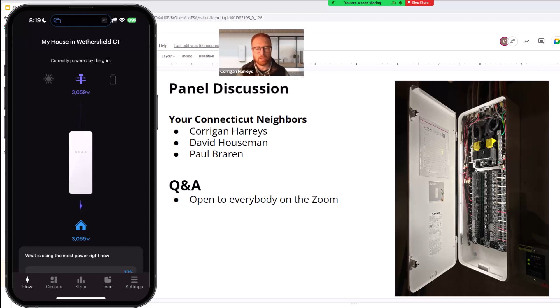Putting in a subpanel is definitely doable, and I've done that. You only get data points on the 2-pole breaker that feeds the subpanel. But most of the time, if there are critical loads in that subpanel, we can take those out and run them directly to the SPAN panel. And if the subpanel is right next to the SPAN panel, you can dump in a bunch of non-critical loads, or loads you don't need to control with the SPAN panel. It's a pretty good option.